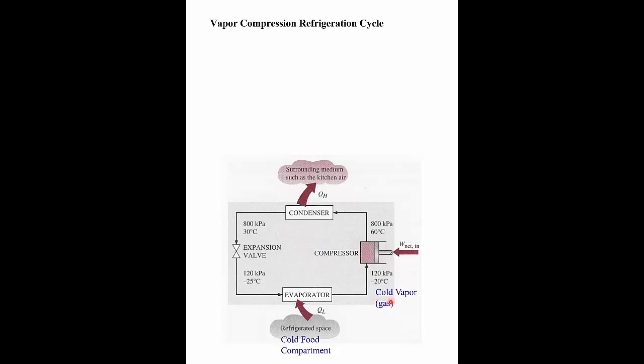We start with cold vapor — for example, R134A. It sets off as a gas and then we put it into the compressor and compress it down. When you compress a gas, it gets hot. So we compress the gas and it goes from minus 20 degrees C to 60 degrees C, and the pressure increases from 120 kilopascals to 800 kilopascals, so to high pressure. The temperature has increased, and up here we have hot gas.